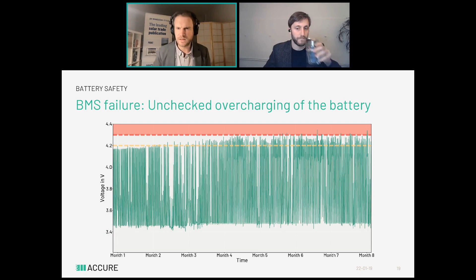That's one of the main challenges we solve, and one of our core IP. What we do is look at the input and output of the battery at all times and how it changes over time. For example, we reconstruct the open circuit voltage curve of a battery purely from operation, and how it changes. From the way that curve changes over time, there are interpretations you can make, down to how much active lithium is still left in the cell, which can translate into a state of health. Of course, the battery needs to do something in order to be monitored in that way.